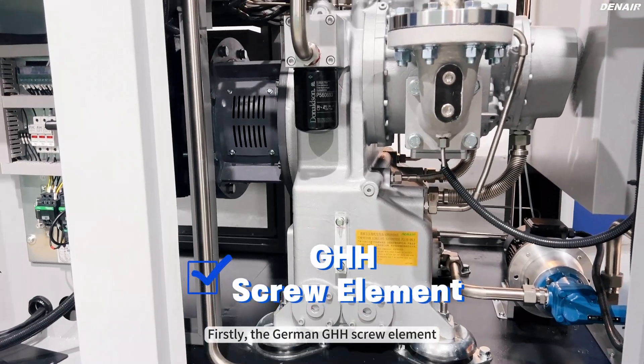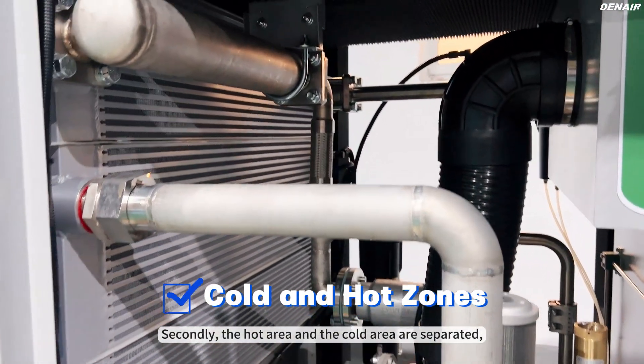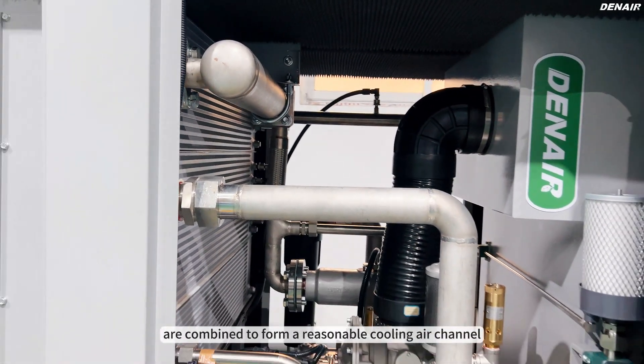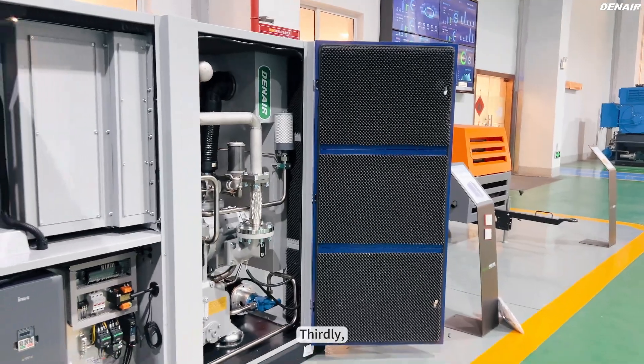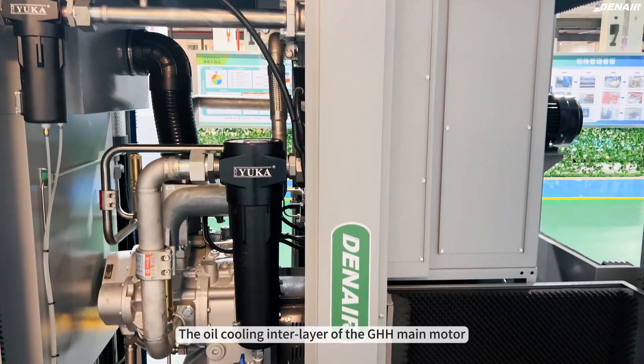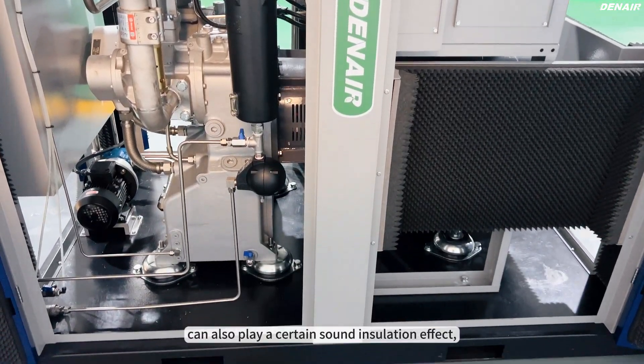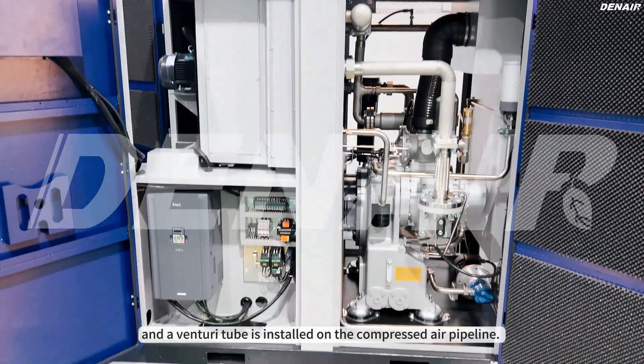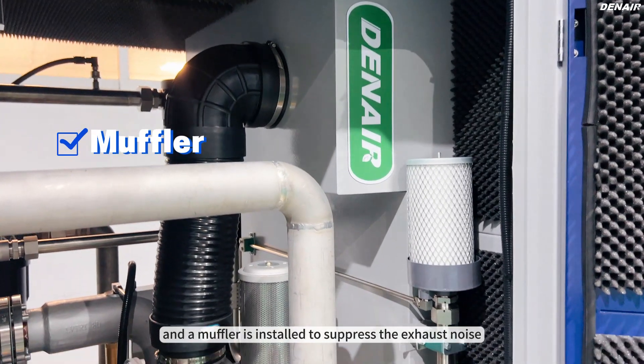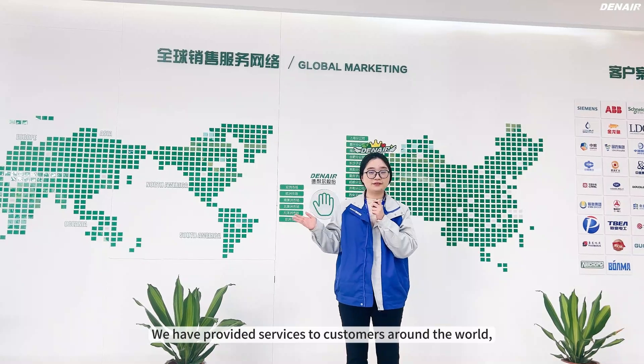Firstly, the German GHH screw element. Secondly, the hot area and the cold area are separated, and the wind inlet and heat dissipation outlet positions are combined for a reasonable cooling air channel inside the machine. Thirdly, each sheet metal is fixed with a fully flame-retardant sound-absorbing sponge. The oil cooling interlayer of the GHH main motor can also play a certain sound insulation effect. A venturi tube is installed on the compressed air pipeline, so the noise is better suppressed when the machine is running, and a muffler is installed to suppress the exhaust noise during unloading.